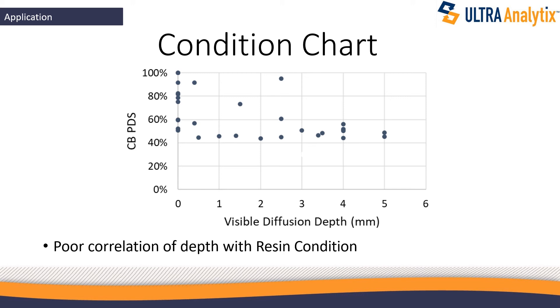We also wanted to know: does the condition of the lining relate to the depth of diffusion? What we found is it doesn't. There's a very poor correlation of depth with resin condition. Most of the time the resin is in worse condition than you really want to know. We've got one case where we have a two-and-a-half millimeter depth of diffusion and it's like brand-new resin — it could very well be that the chemical involved is almost meaningless. But we know that we can see two and a half millimeters of damage in it.